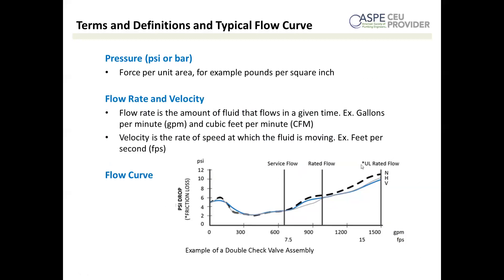UL rated flow is 150% of rated flow and is not recommended for continuous duty. This is typically only used for fire systems where you should either have no flow or, in case of a fire, extremely high flow — now you're drag racing. Also notice on the right-hand side the N, H, and V designations, which correspond to three different orientations for a backflow preventer: an N pattern (flow up, across, and down), a horizontal installation (flow left to right), or a vertical installation (flow bottom to top). These all have slightly different performance characteristics.